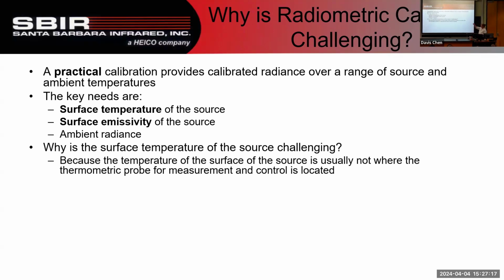What do you do? You put the temperature probe inside something, inside the big metal plate that you're going to measure in the black body, but now you're measuring the center of the plate, not the surface. So what happens is this temperature measure is the well temperature, and there's a gradient between that and the actual temperature of the surface, right? The room's cooler, so the temperature of the surface is going to be a little cooler than what you measure in the well.